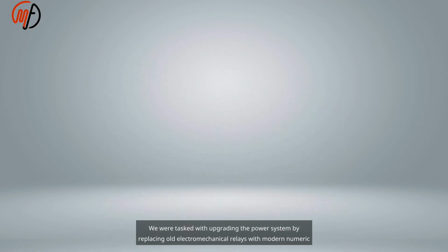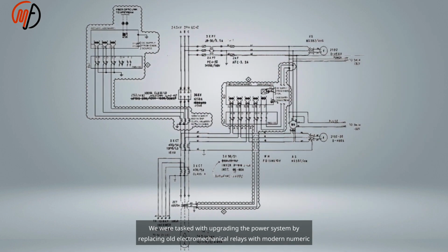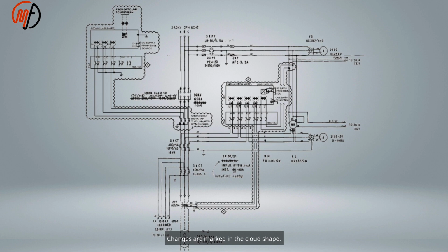We were tasked with upgrading the power system by replacing old electromechanical relays with modern numeric ones. We modified the CT and tripping circuits, adding new CTs for line differential protection on the 34.5 kV line. Changes are marked in the cloud shape. The image shows the modified tripping circuit with modern relay contacts. The second generation, static or solid-state relays, emerged in the early 60s with no moving parts, reducing operational errors.